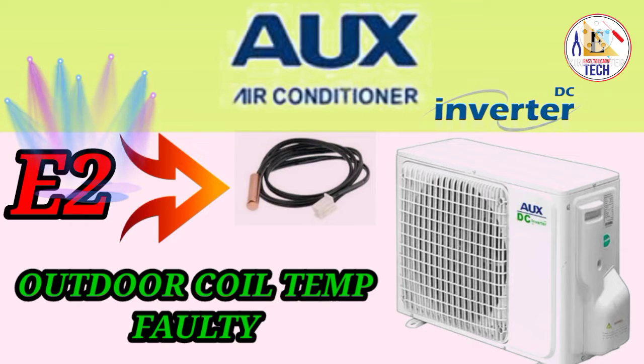If the placement and the connection are good, then you have to check the resistance of your coil temperature sensor. If the resistance is not good, you need to change the coil temperature sensor. If the resistance is good, then check in your outdoor PCB if the output supply coming from the outdoor PCB to the sensor is good or not. If it is not good, then you have to change the outdoor PCB and you will get the solution for the error E2. And your unit will be working normally.